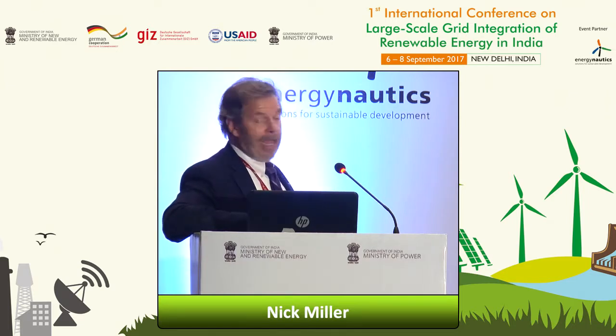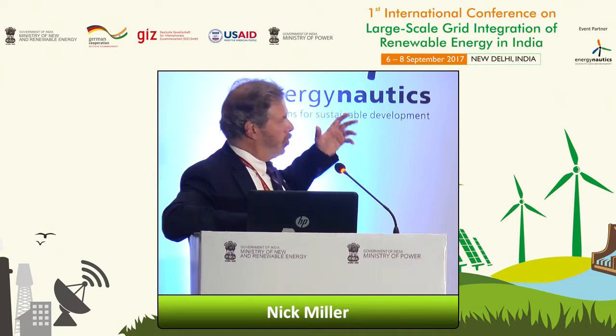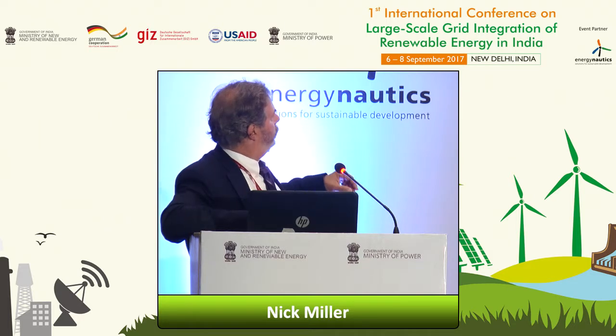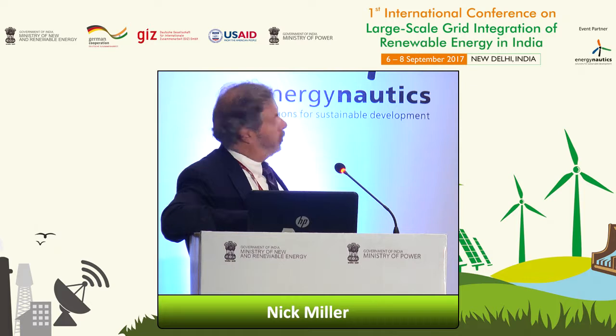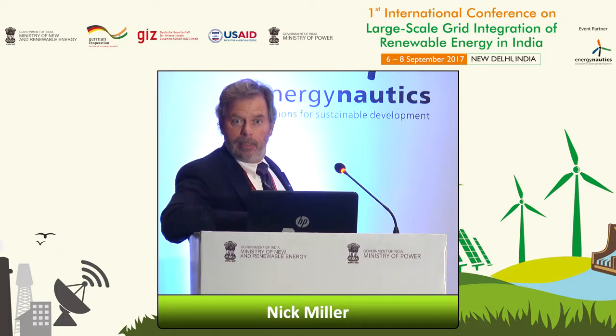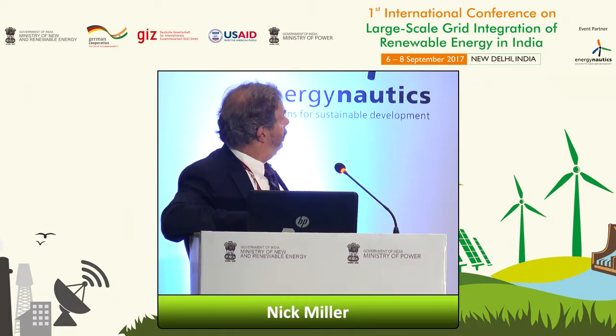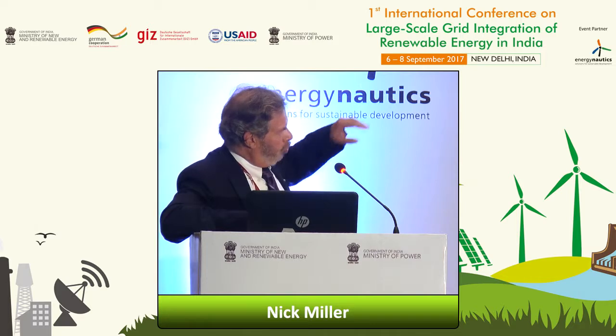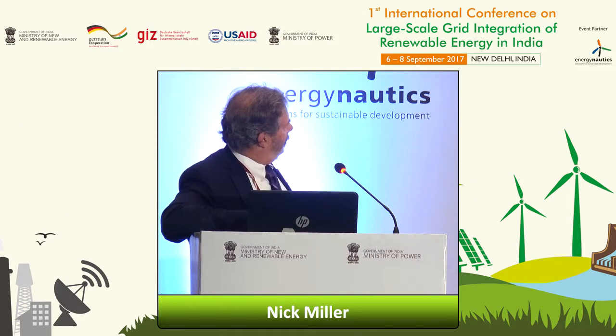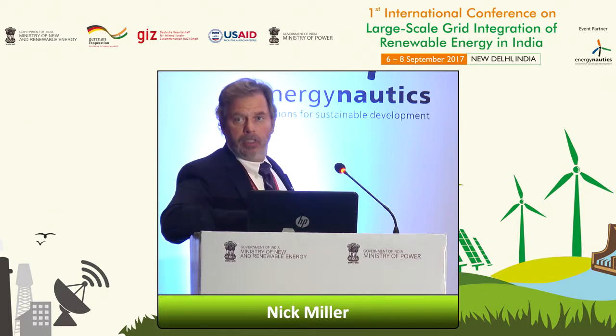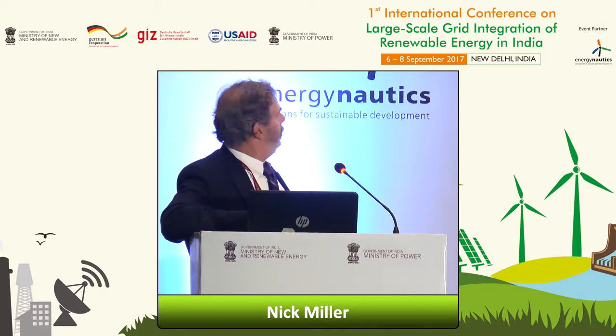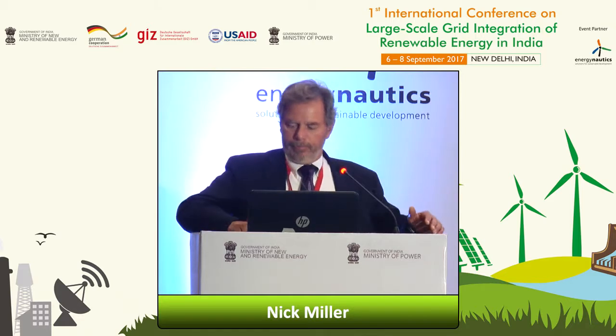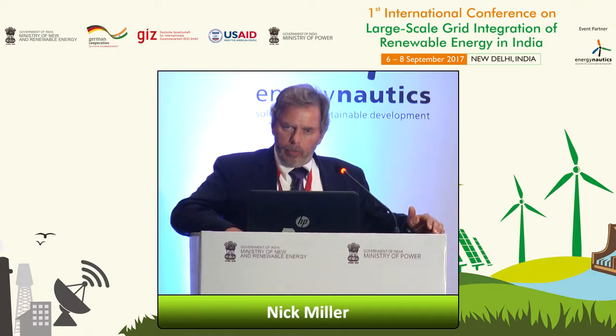So we're banging the system. This is the total VARs. The way you want to read this, this is 1 second across here — that's the stimulus, and that's the reset. So the response is indeed 1 second. There's a little bit of droop going on in there, so the fact that it's not exactly there is not a violation of the objective. This is up, this is down. We did it, okay? So you can get there, but you really have to be careful.